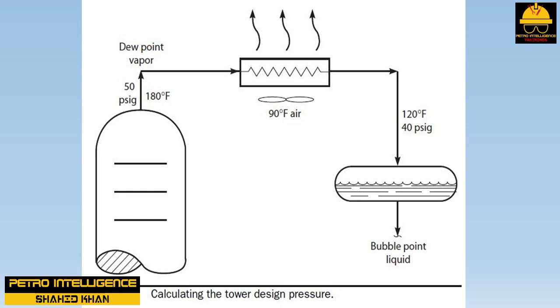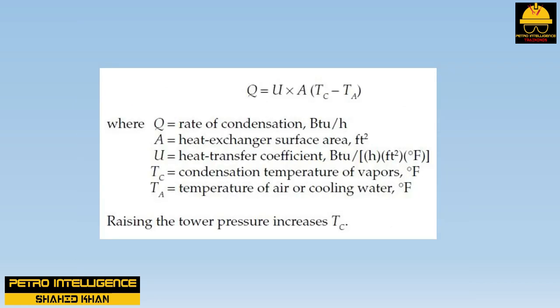Another reason to raise tower pressure is to permit higher reflux rates. If the pressure controller is set too low, then during hot weather, when condenser capacity becomes marginal, the level in the reflux drum will be lost. If we then raise the pressure set point, the drum will refill. Raising the tower pressure also increases the reflux drum pressure, raising in turn the temperature at which the vapors condense. The rate of condensation is calculated from: Q equals U times A times (TC minus TA), where Q equals rate of condensation in BTU per hour, A equals heat exchanger surface area in square feet, U equals heat transfer coefficient in BTU per hour square feet degree F, TC equals condensation temperature of vapors in degree F, and TA equals temperature of air or cooling water in degree F. Raising the tower pressure increases TC.